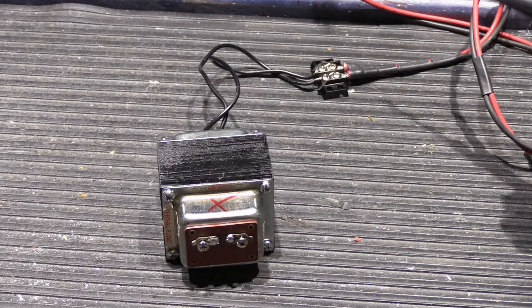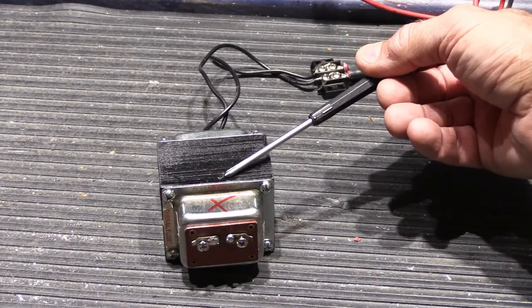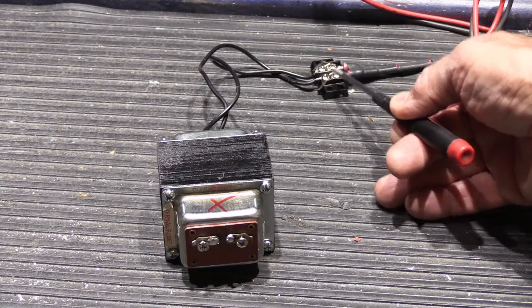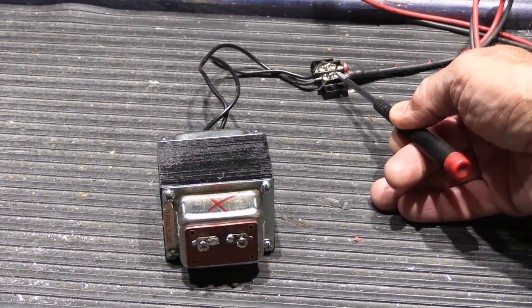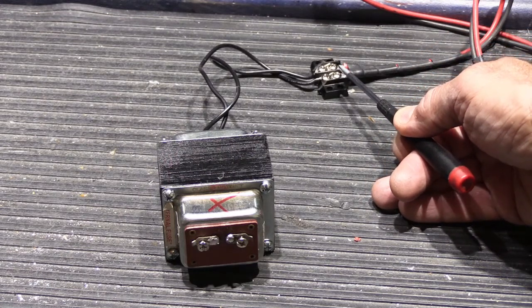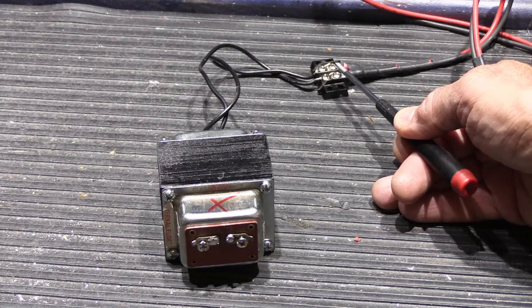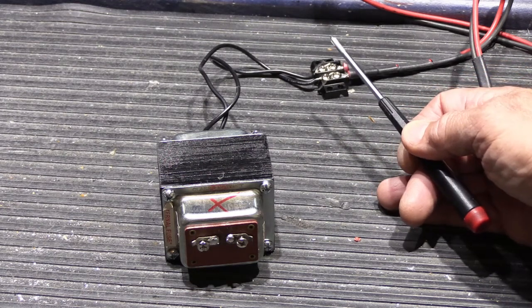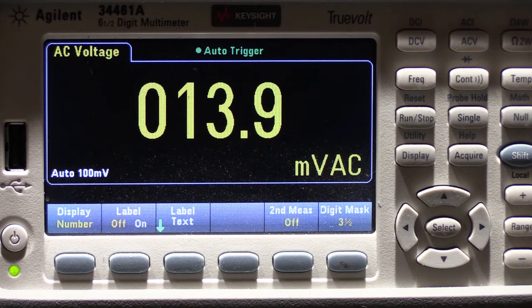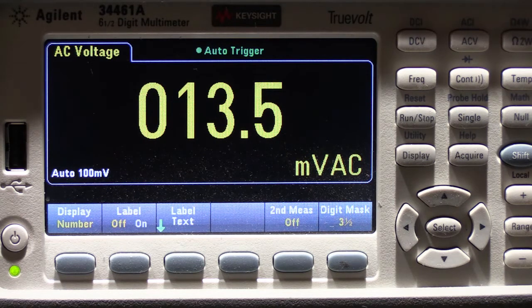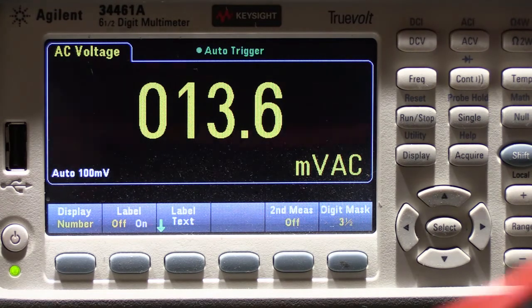Here's the setup. I have the 801T that we just repaired, wired to my bench AC power supply, set at 115 volts. We're going to turn this on, but first I'll show you the voltage on the meter. You're looking at the display readout on my Agilent/Keysight 34461A multimeter, everything turned off and the probes not touching anything.